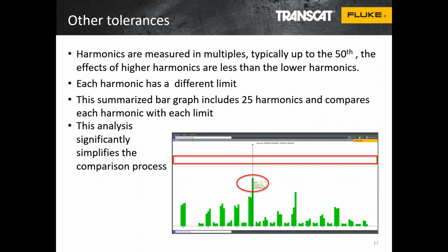It's not causing too much of a problem, and won't really be an issue for us. But what the limit line is doing is that each of the levels for all the harmonics is different. So, for example, the third harmonic level and the fifth harmonic level have a similar magnitude, within the region of 3% each.